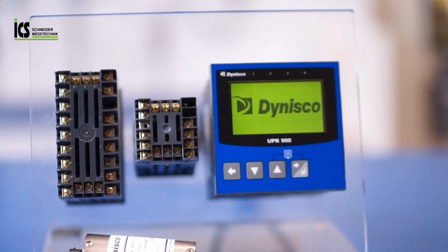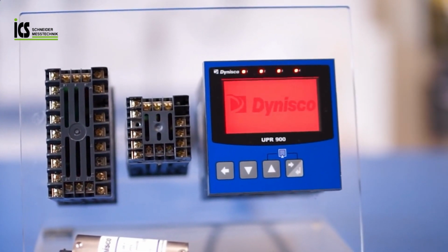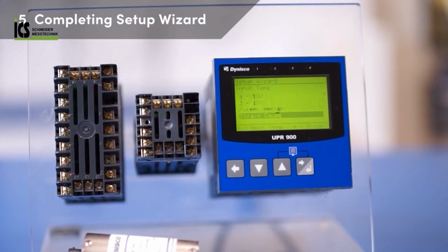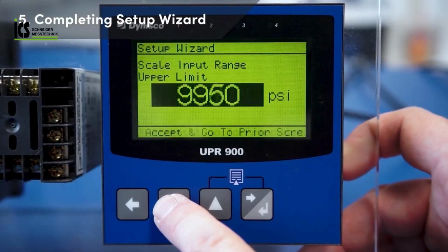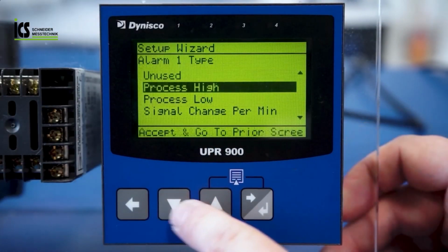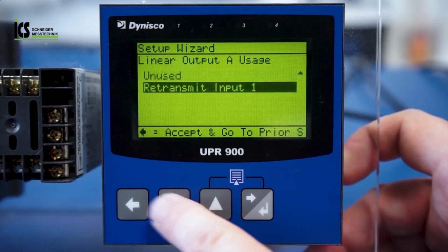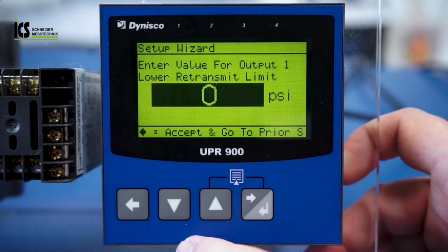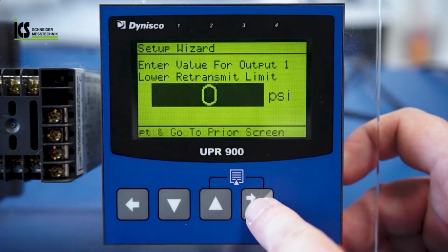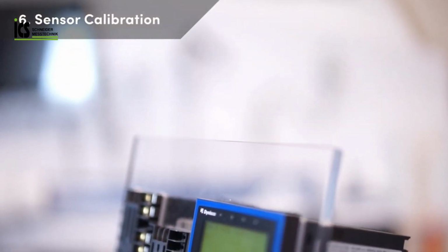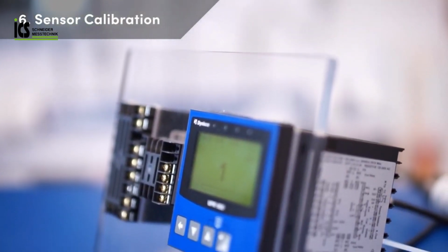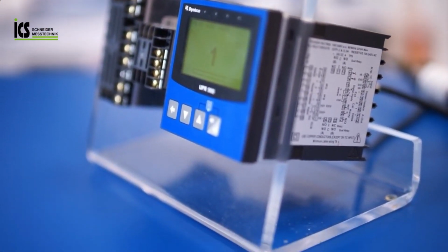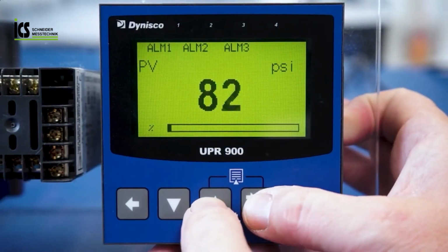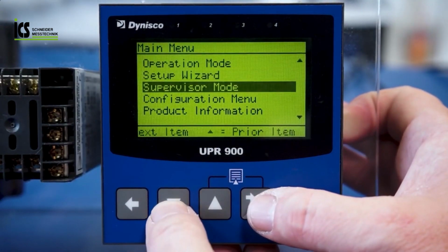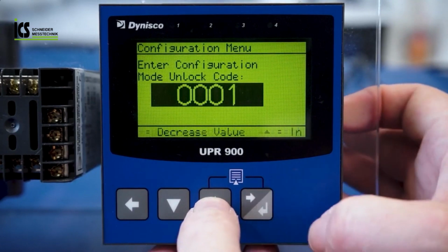With the sensor connected, it is now safe to supply power to the instrument and then enter the setup wizard function of the instrument. The technician now enters the appropriate parameter settings to match the pressure sensor output range, desired alarm settings, retransmission signal, and other attributes such as peak pressure detections and optional data logging. Dynisco recommends that the pressure sensor be brought up to process temperature with 0 pressure applied for calibration with the process instrumentation. The technician enters the sub-menu to access the configuration screen and then enters the default unlock code of 0001.